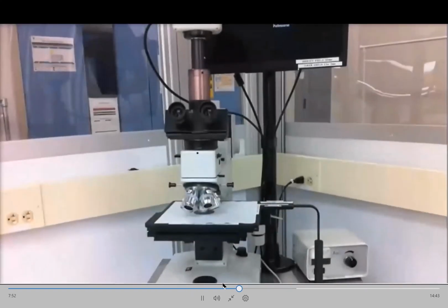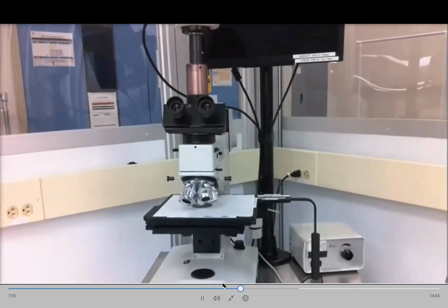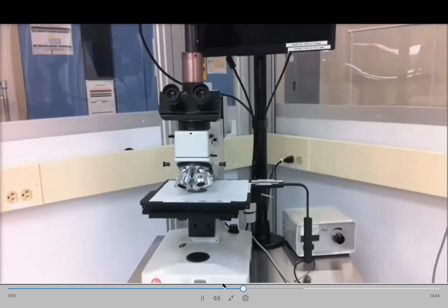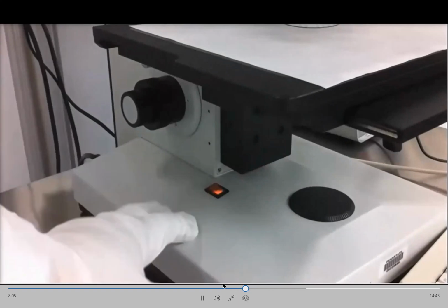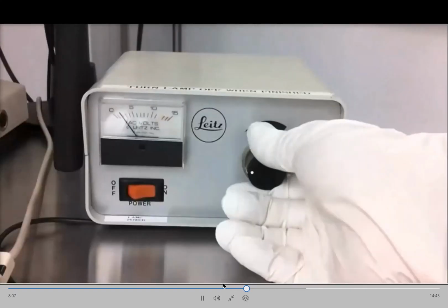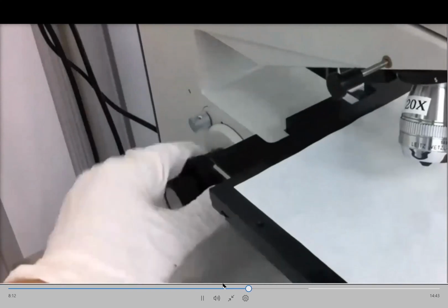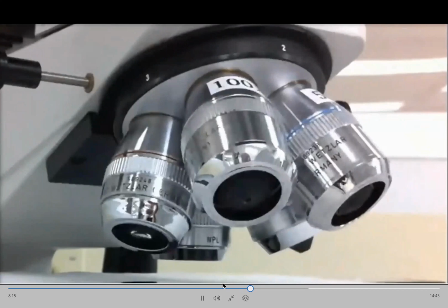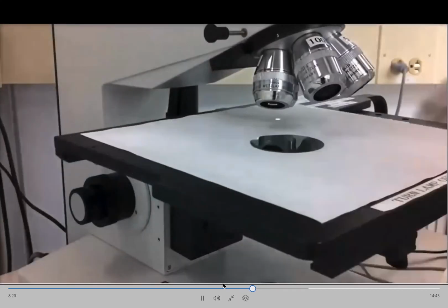All right, now that we've reviewed the major components, functions, and safety concerns of optical microscopes, let's get started and image a sample. Turn on the microscope power and the light source, lower the stage to a safe working distance, rotate to the lowest power objective lens, load your sample, and move the stage to the proper position below the lens.